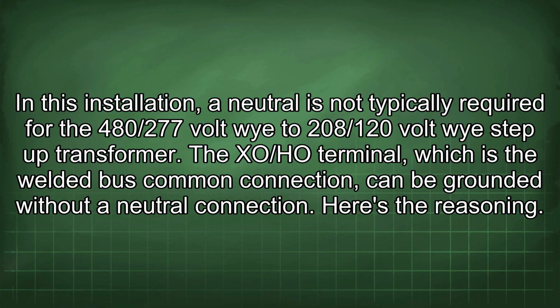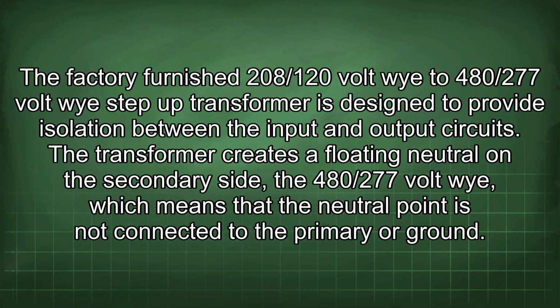Here's the reasoning. The factory furnished 208/120 volt Y to 480/277 volt Y step-up transformer is designed to provide isolation between the input and output circuits. The transformer creates a floating neutral on the secondary side, the 480/277 volt Y, which means that the neutral point is not connected to the primary or ground.